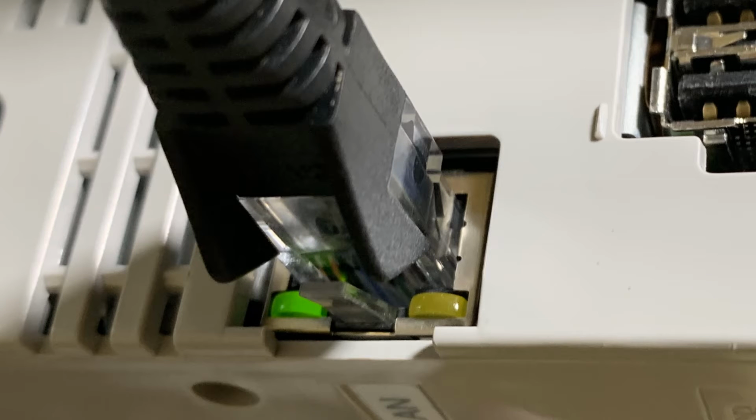So this picture is showing the Ethernet port on the touchscreen or the touch panel, and we can see the Ethernet cable plugs in there. It's either a black or a blue short cable, and there's two little lights on there, a green link light and then an amber activity light, and hopefully we see both of those lit up. That means it's showing communication.